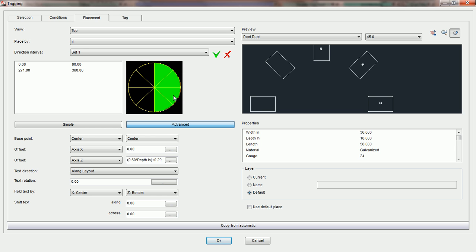So if you would like to get tags on ducts that are going in an elevated view, you would need to check use default placement. And when you do that, it will place the tag but it will place it in the center of the fitting. That's where the default placement usually is.